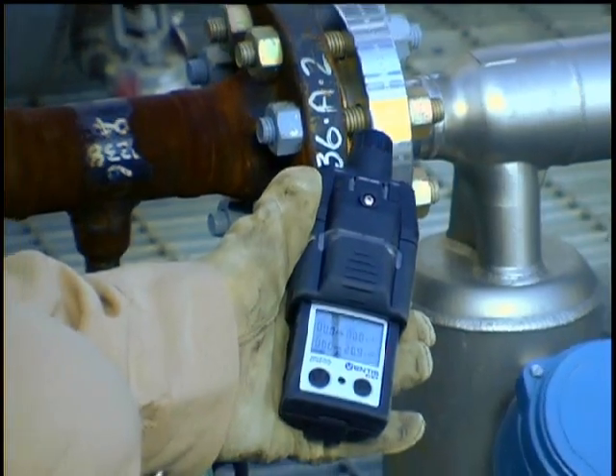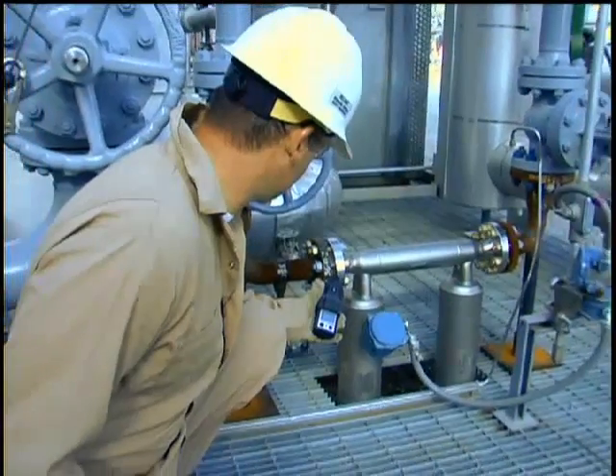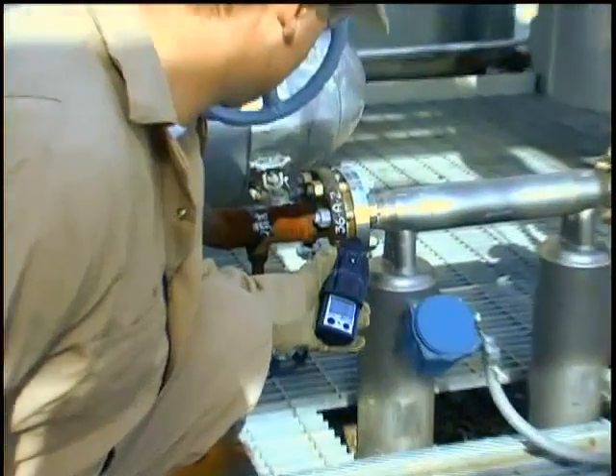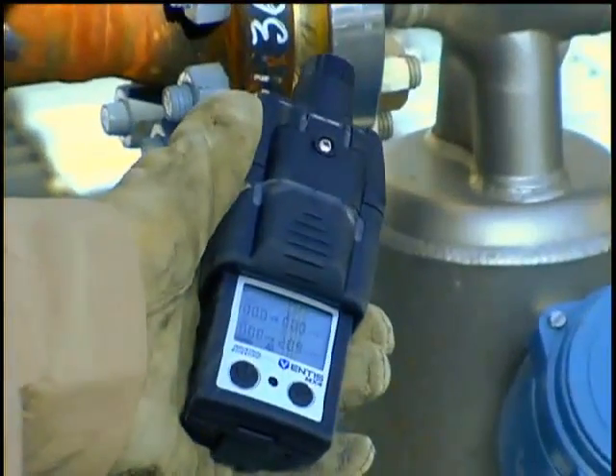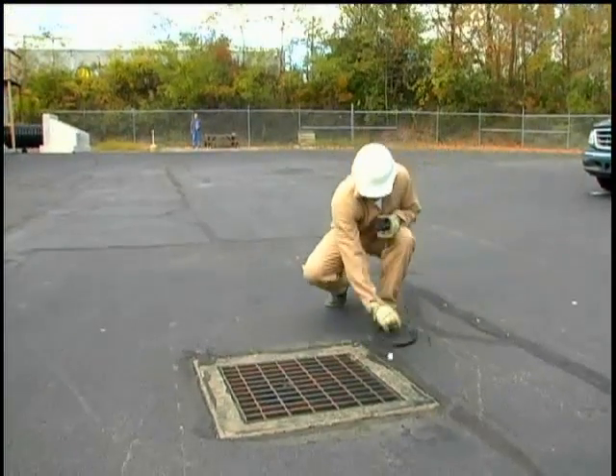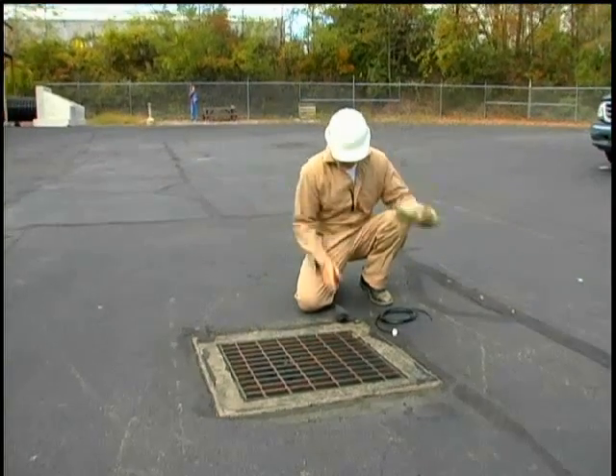The Ventis MX4 is designed to be a personal gas monitor, but when combined with a sampling pump, it can be used to draw a remote sample from a maximum distance of 100 feet while using 1/8th inch inner diameter tubing. Once installed on the Ventis MX4, the pump automatically powers up when the instrument is turned on.